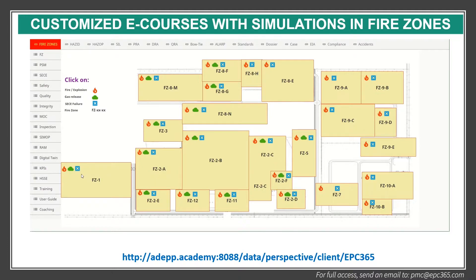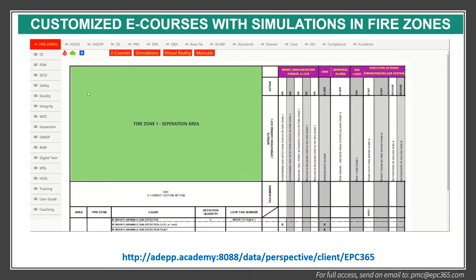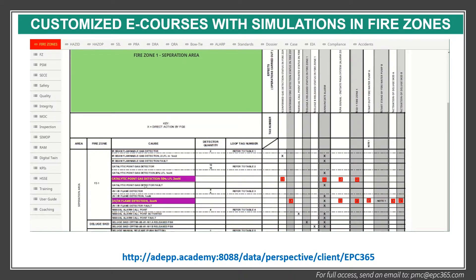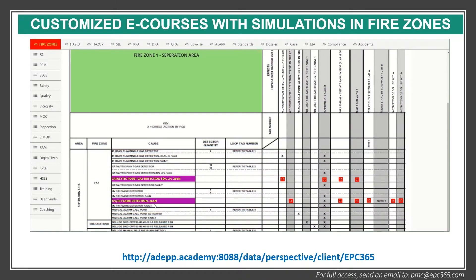For each fire zone there are three icons: fire and explosion, gas release, and failure of safety critical elements. If you click here, you will go to the installation view. Here you can see there are three flame detectors. There will be a cause and effect matrix showing, for example, what actions will occur in case of fire detection — for example, if there are UVIR flame detectors with 2-out-of-n voting, what will be the actions. The actions normally include a mimic on the annunciation panel in the control room, operator workstation, general alarm, ESD logic, and executive action. For example, if there is a confirmed flame detection, the fire water pump A starts and the deluge system starts.